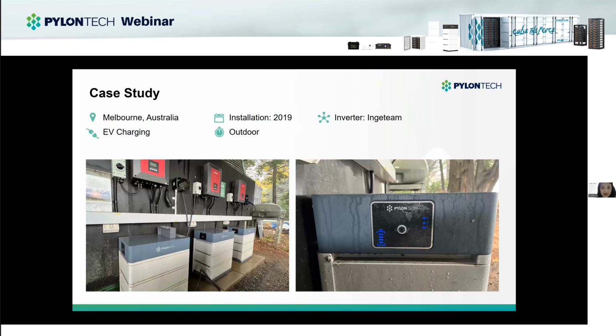This is an example in Melbourne, Australia. At first, the user put the battery indoors as residential storage. Later, due to demand changes, he moved the battery outdoors and covered it with a shed for backup EV charging. From this picture on the right, you can see that there is some water on the surface of the battery, but it doesn't affect the normal use of the battery. This system has been running stably for more than 3 years.